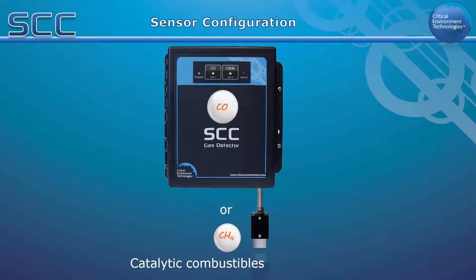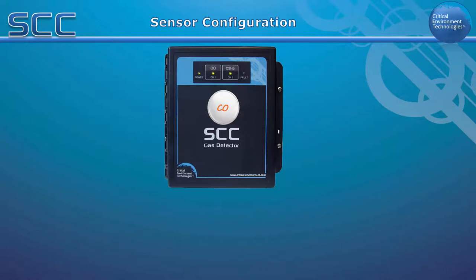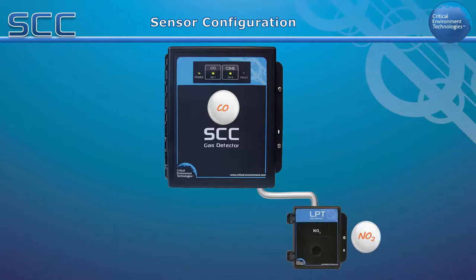It can have one internal CO sensor and one external catalytic sensor. Monitoring of CO or NO2 may also be achieved remotely by combining the SCC with a 4-20 milliamp transmitter, such as the LPT-TCO or the LPT-END.